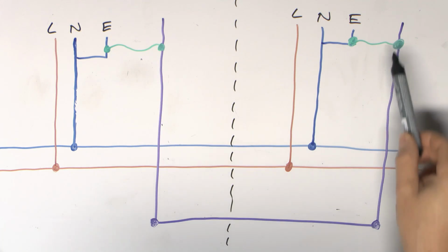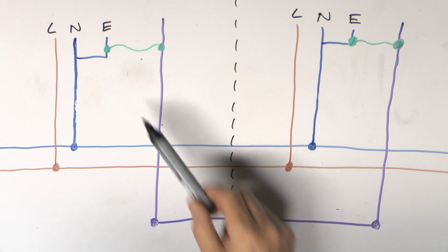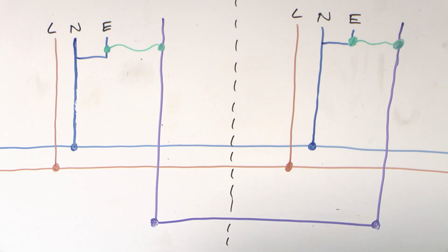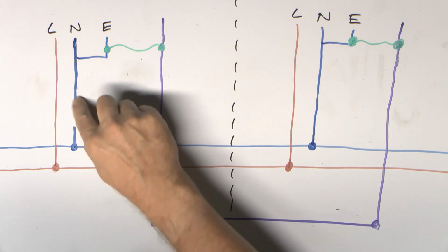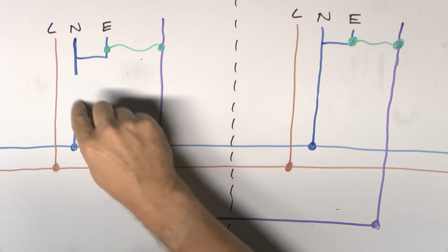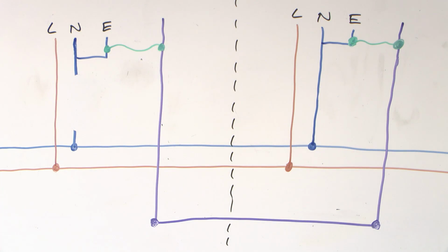Inevitably some current is going to go via the shared metal pipe because eventually it's a parallel path to both the supplies, but as we saw previously, that's pretty much normal and expected. But what happens when this conductor here gets busted, either due to someone damaging it or more likely some 50-year-old connection out in the road corrodes away and disintegrates? What's actually going to be happening now?